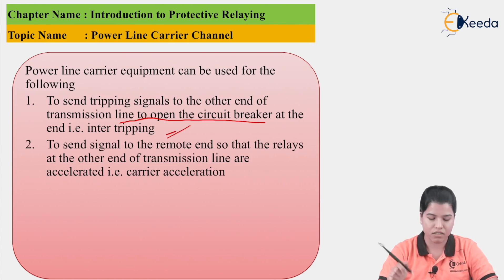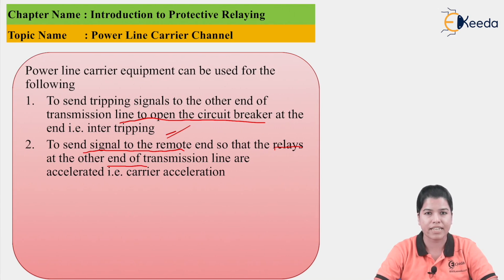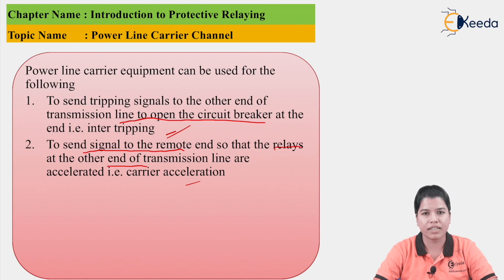Next is to send the signal to the remote end so that relays at the other end of the transmission line are accelerated. This is called carrier acceleration. When fast tripping operation is to be performed, the relay operation should be accelerated. The power line carrier channel can be used to send the signal from the sending end to the receiving end to the relays so that relay operation can be accelerated.